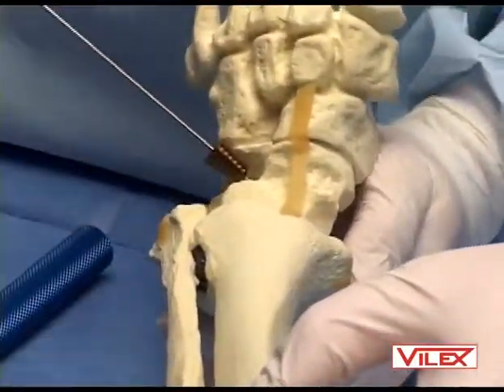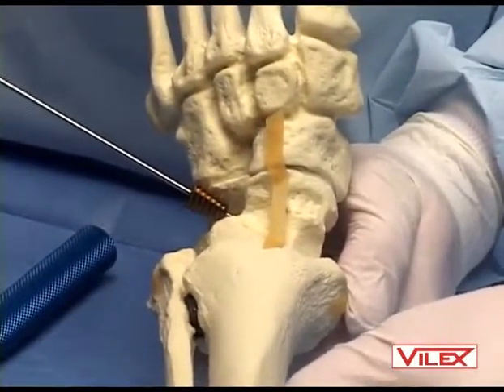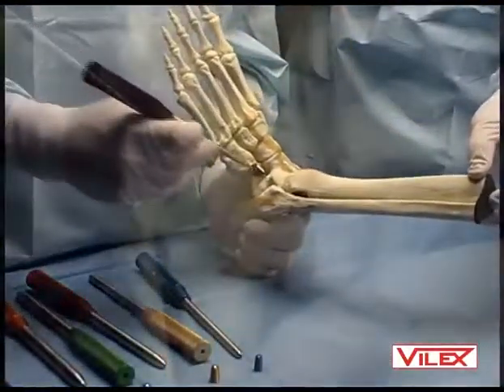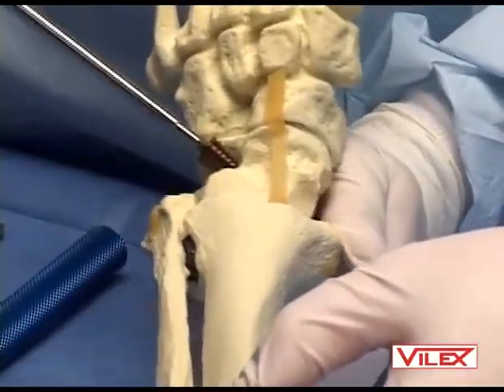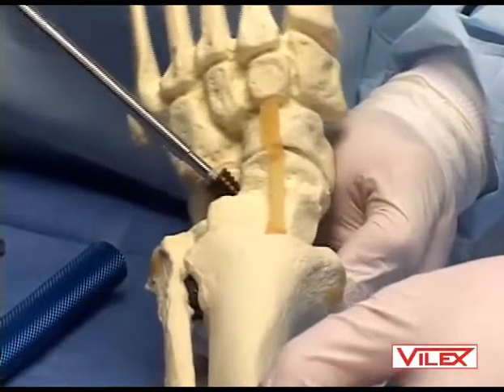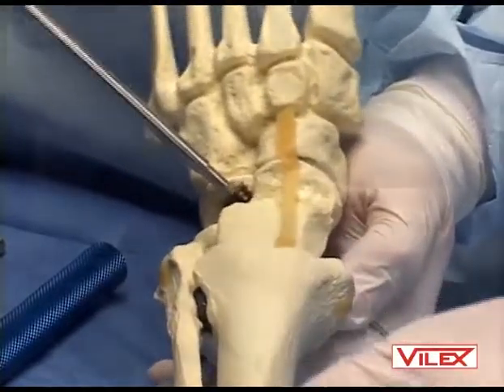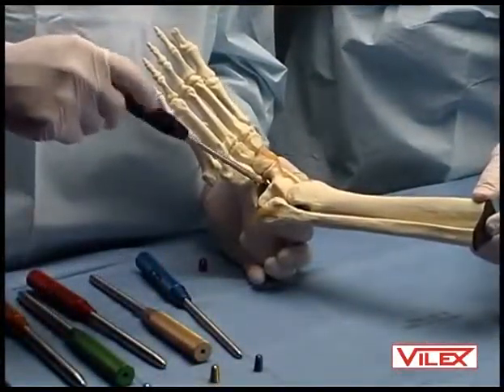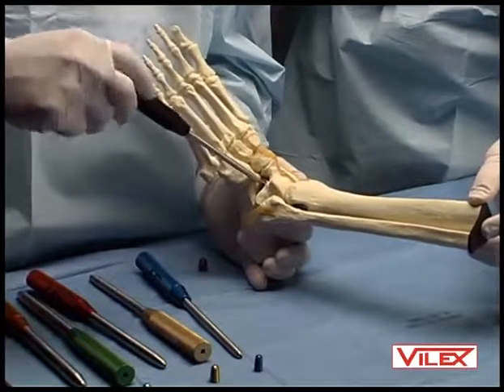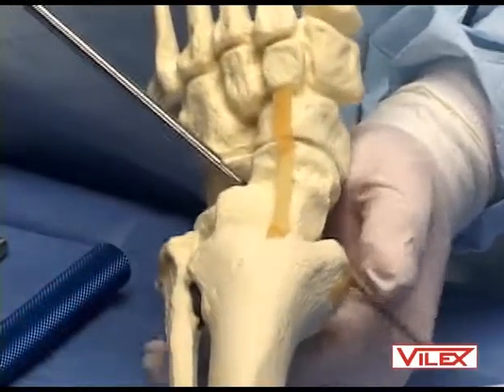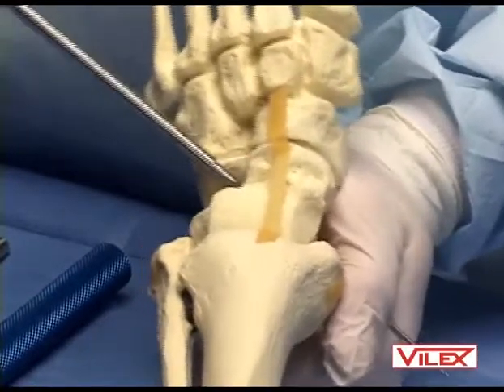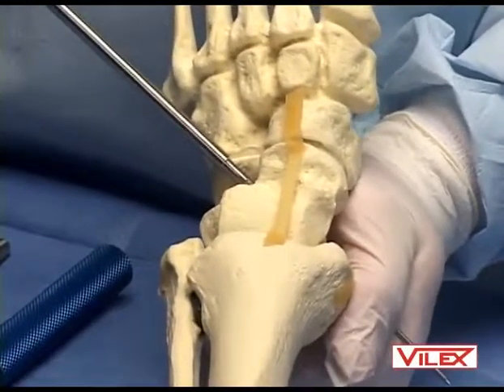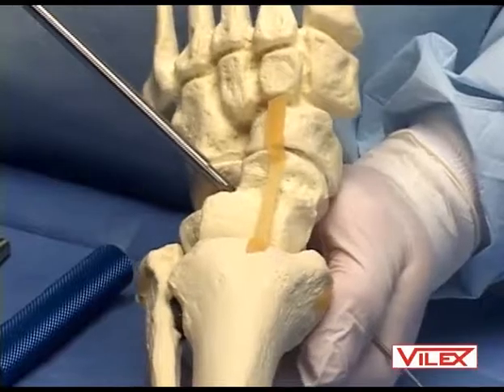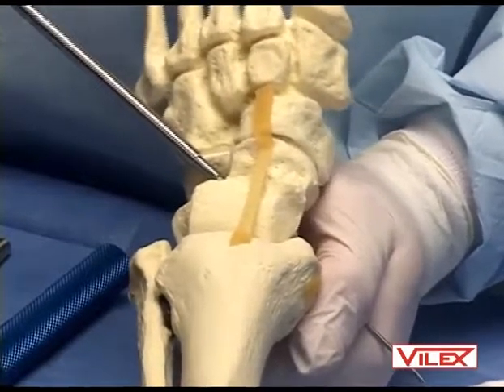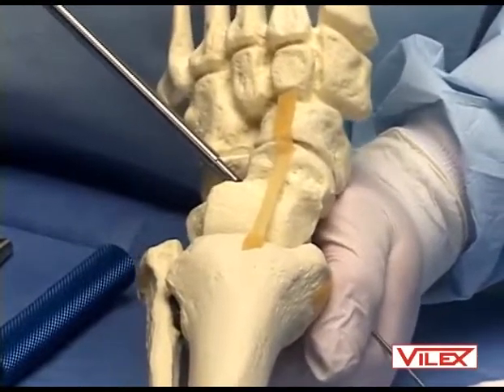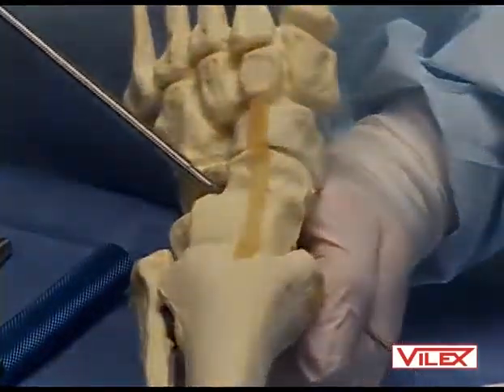And as you can see, as the sizes get larger, the conical design is more absolute. And in this case, I can advance it so that only the middle of the actual implant, rather than the trailing edge, is at the bisection of the talus. It's probably the number one reason for explantation when an implant's placed too far medial beyond that bisection. Your better position would be to go to a larger size than to advance it too far medially.